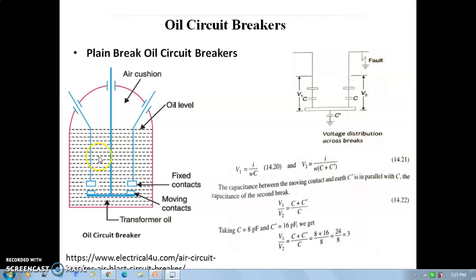Due to arc energy, heat is formed. Whatever oil is there, that is decomposed and produces hydrogen gas. That hydrogen gas surrounds the arc between the two contacts. We have to maintain the space between them and the elongation of the arc. Whatever arc is formed, we have to elongate it so we can reduce the arc.